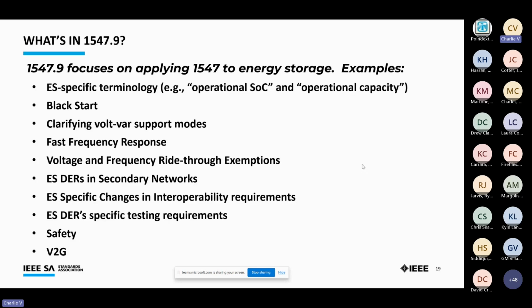Clarifying voltage VAR support modes for energy storage. Energy storage can, in its operational flexibility, go beyond the operating curves of 1547-2018, and this guide shows how you would be 1547 compliant with a full four-quadrant device that is not just positive and negative injection for reactive, but positive and negative injection for real power. By prudently accessing those capabilities, it extends the grid support goal that was part of the 1547 update.